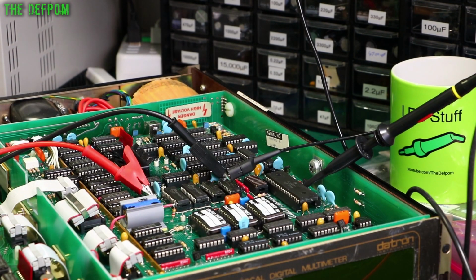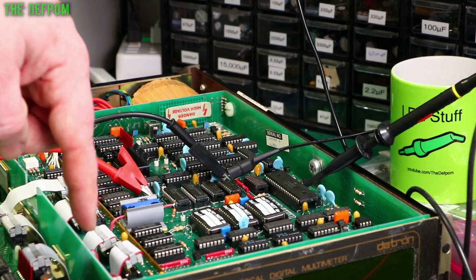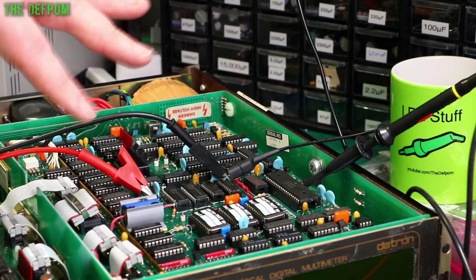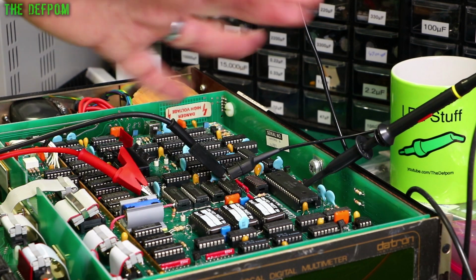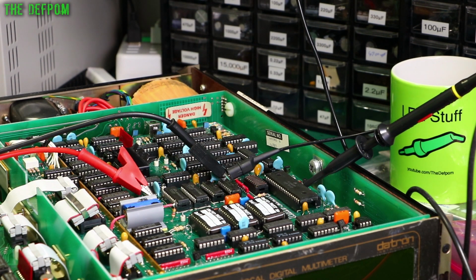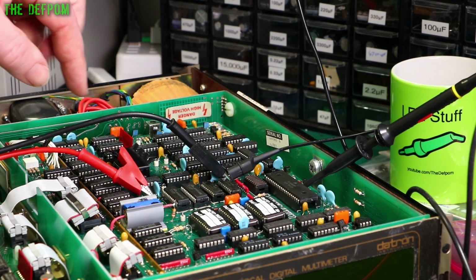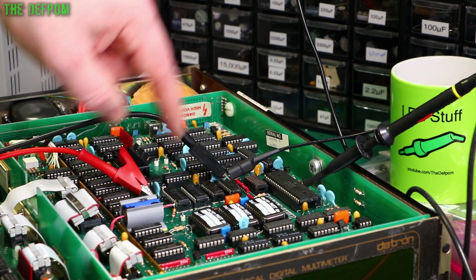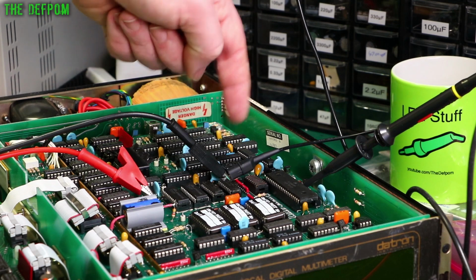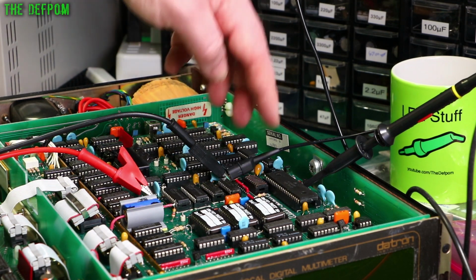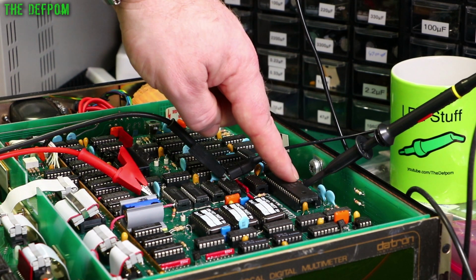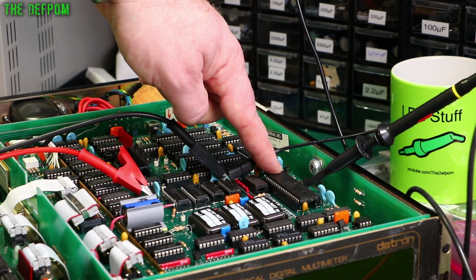Alright, so the test point I'm doing now is one of the digital board assembly sections. So this is the first step, which is to disconnect all these ribbons and stuff down the side, down the centre plane. So there's no supply, obviously no power on the unit either, it's all turned off. I'm injecting 4.75 volts into the test points, which is TP8 over here and TP28, which is 0 volts ground. And I've got my scope probe hooked up here, which goes to this test point over here, which actually goes to pin 40 of this chip.